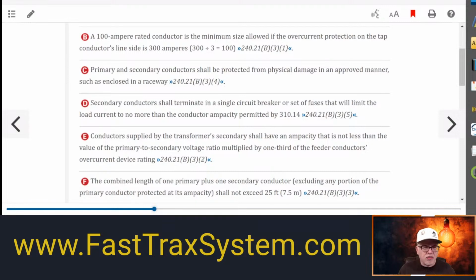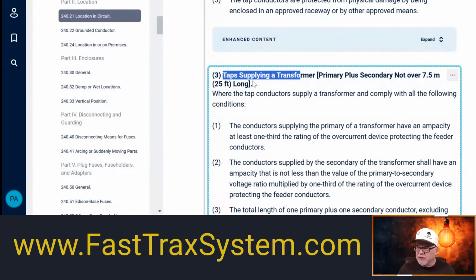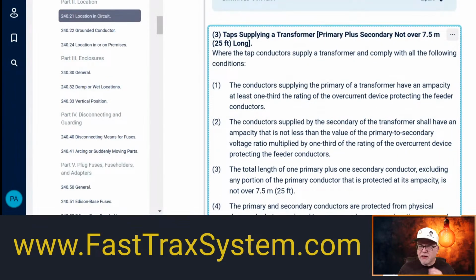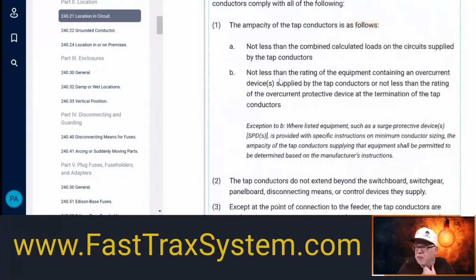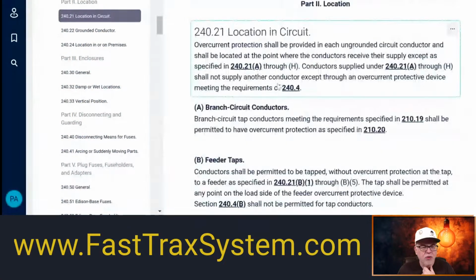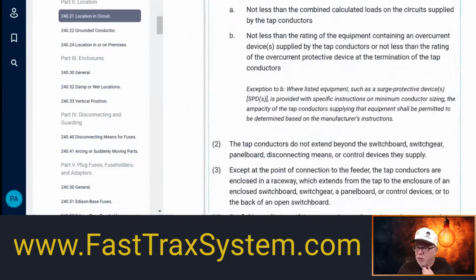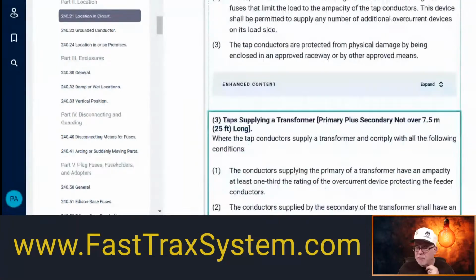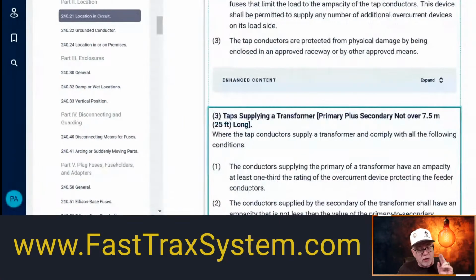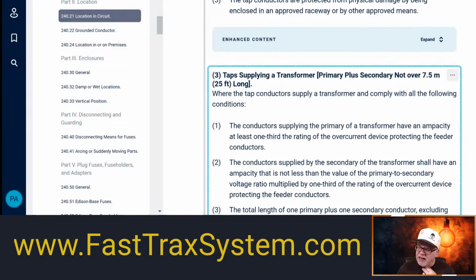Taps supplying transformers. Oh, I got to share the page, that way you can see it. So for those that are following along in your code book, we're at 240.21. And we're down, and we're still at feeder taps. We're at B. We're not at C. That's secondary conductors. They are not taps. Those are secondary conductor rules. We're at taps. All right, so here we have taps supplying a transformer. That is the primary plus the secondary, not over 25 feet long.